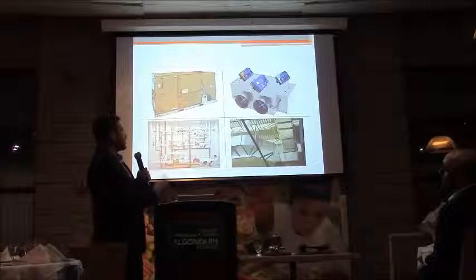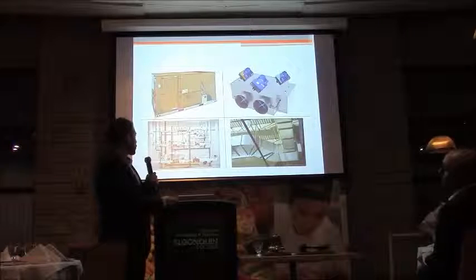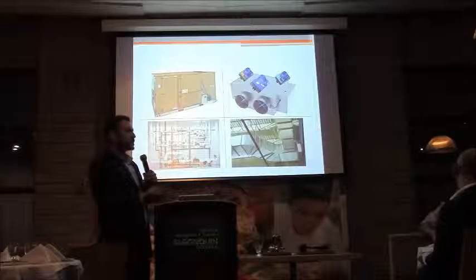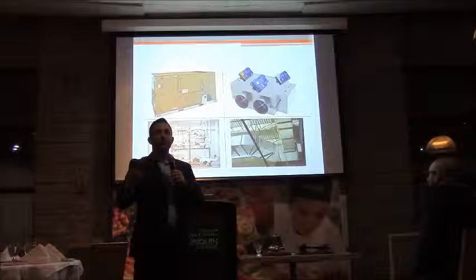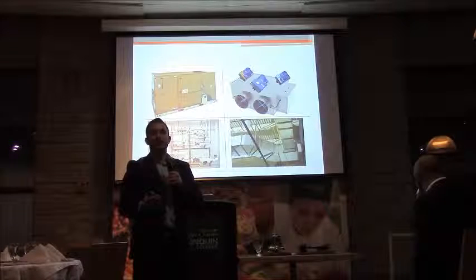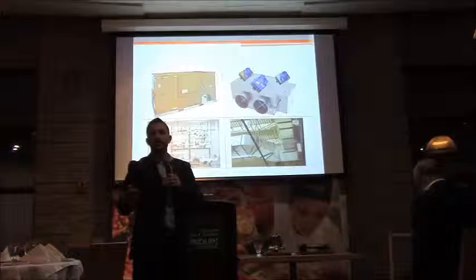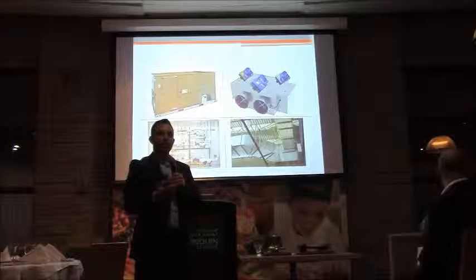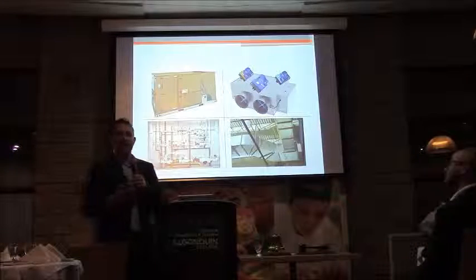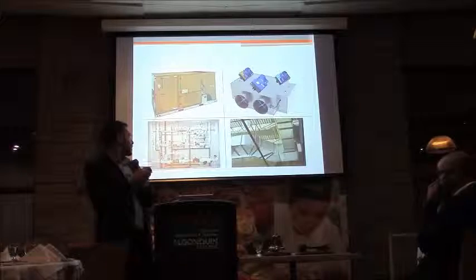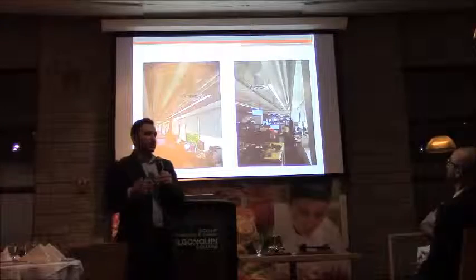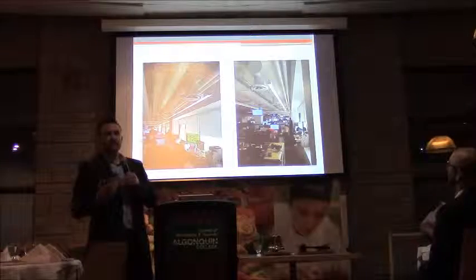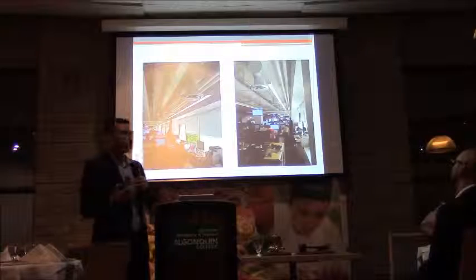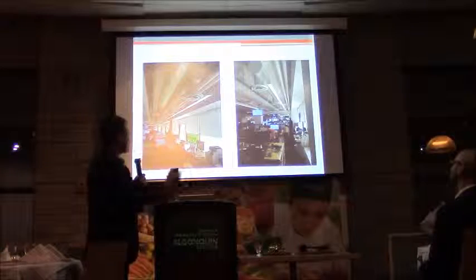And we invest just as much money in high efficiency controls, we insulate our piping, we insulate our ductwork, all for the purpose of energy savings. But if we don't properly select our air outlets, then the whole system can be viewed as a failure. And when I say failure, it's not that the system is not going to function properly. I mean it more in the sense that you're going to see things like that.